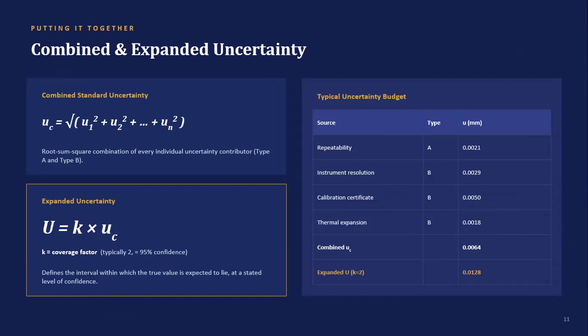We then calculate the expanded uncertainty using the following empirical relationship as illustrated below. Here in this equation, K is the coverage factor. A coverage factor of approximately 2 is commonly used for an interval corresponding to roughly 95% confidence under approximate assumptions. The uncertainty budget presented in today's session highlights the contribution from repeatability, instrument calibration, instrument resolution, and thermal expansion.